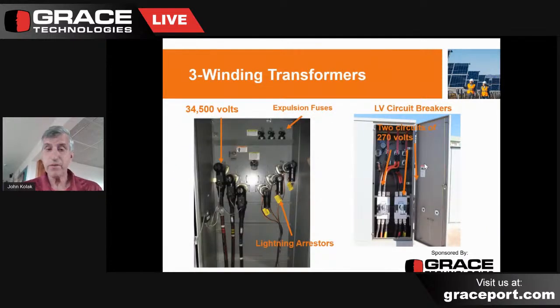Now, another rather unique piece of equipment that you rarely see except on solar farms is a three-winding transformer. Now, again, with transformers on solar or wind farms, we don't use primary versus secondary vernacular. We're going to use the high voltage side versus the low voltage side because the source varies. When a system like a wind farm is not generating, the source could actually be the substation feeding it. That can change when the generators are actually generating at full output. But I got this picture because it's a really good picture for a solar farm because it illustrates several different pieces of equipment that you often don't see except on solar farms.